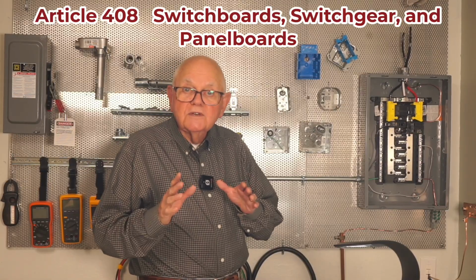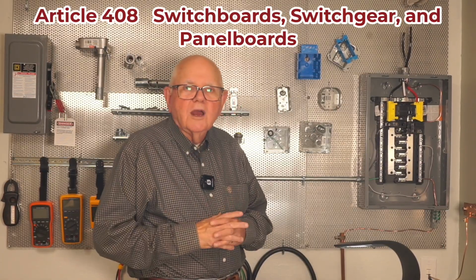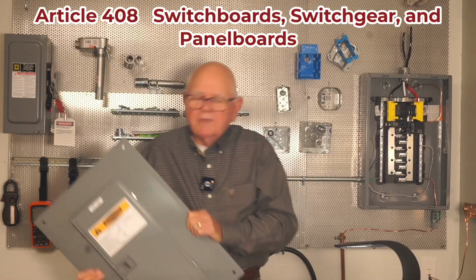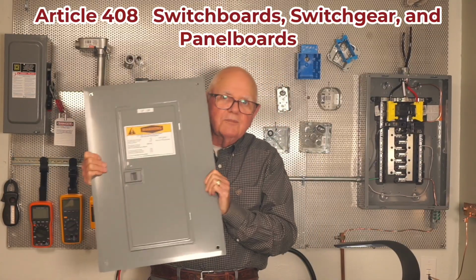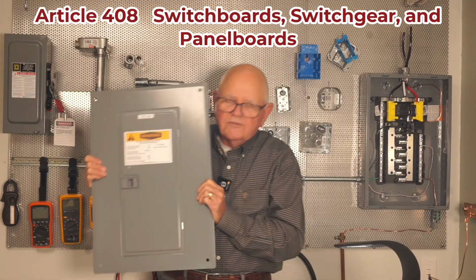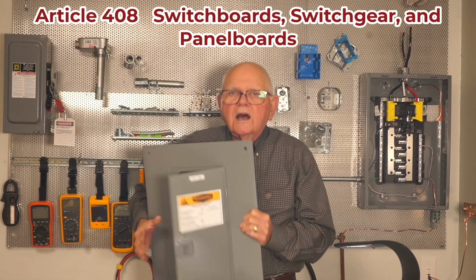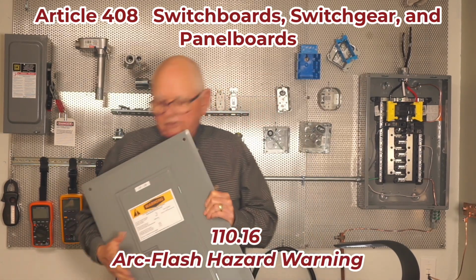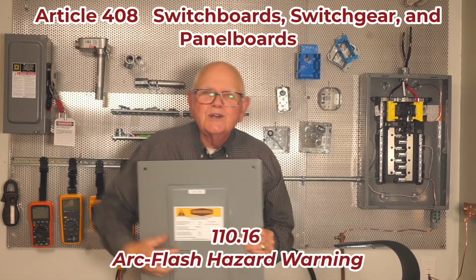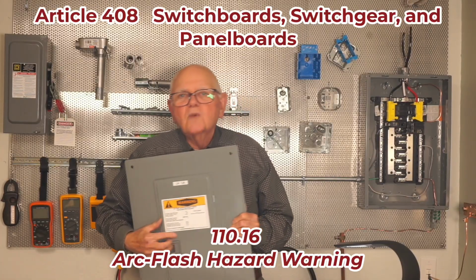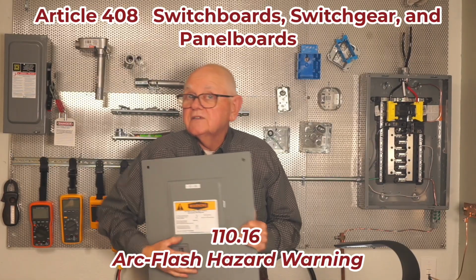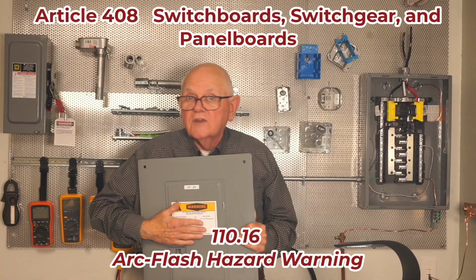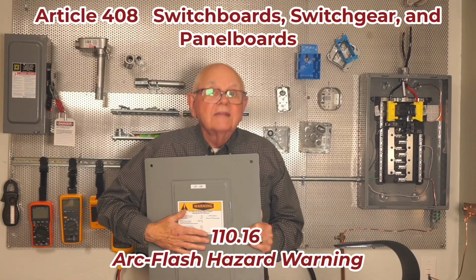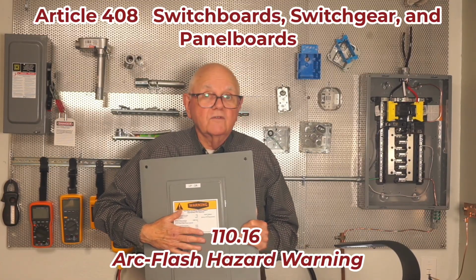So let's move into Section 2, marking requirements. I'll just hold up a cover here of this particular panelboard. There are a couple of things that we have to have on the cover of our panelboard. Other than dwelling units, 110.16 of the NEC says I have to have an arc flash warning label on my equipment. That label is going to have 2 bits of information on it.